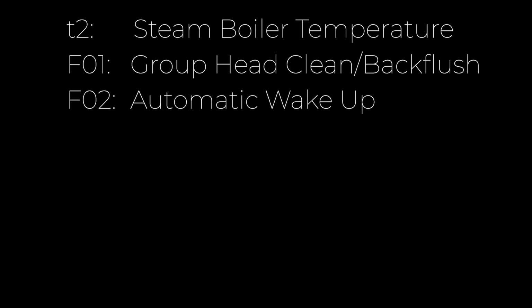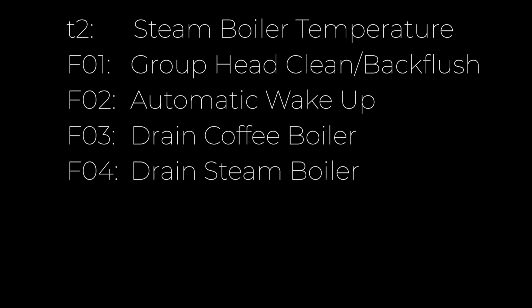T2, that's going to set the steam boiler temperature. F01 starts a 3-step group head cleaning with back flushing. F02 manages automatic wake up. Basically with that, you can put the machine in standby and then it'll wake up after a set number of hours. F03 and F04 are used to drain the coffee and steam boilers.